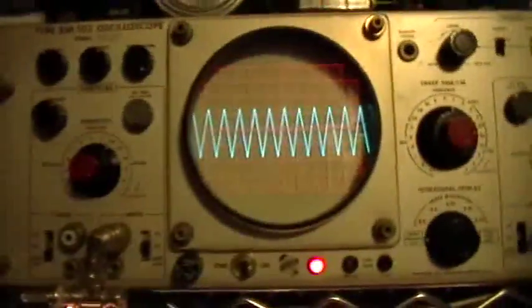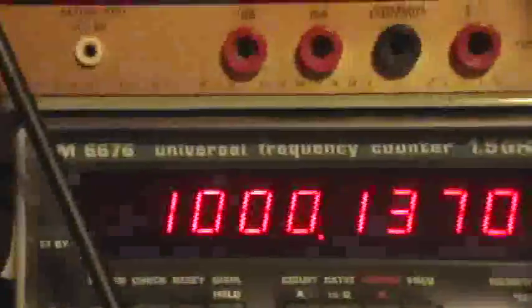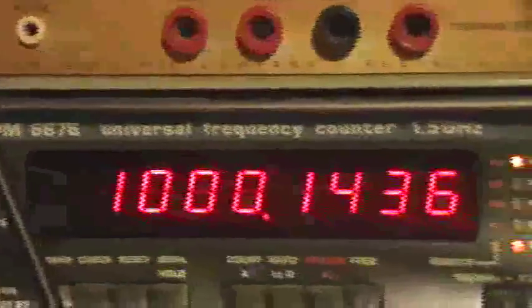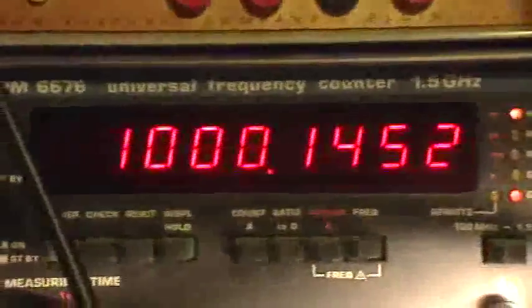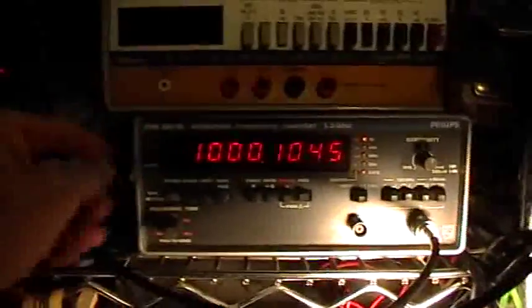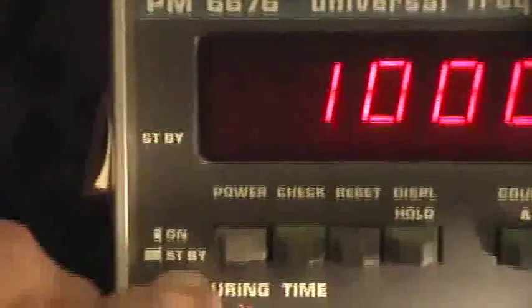So what I have here - I don't know if you can see that or not - this is a Philips PM 6676 universal frequency counter. Inside that Philips frequency counter there's a little crystal oscillator that is actually in an oven. So whenever the unit is plugged in, that oven is keeping that little crystal oscillating at the correct temperature so that it's stable.